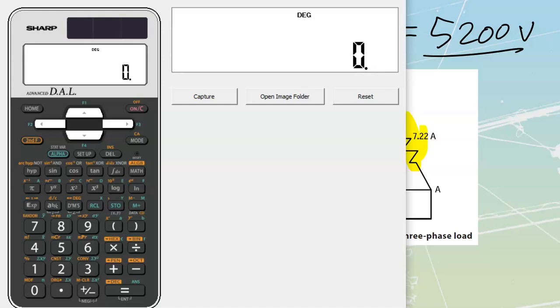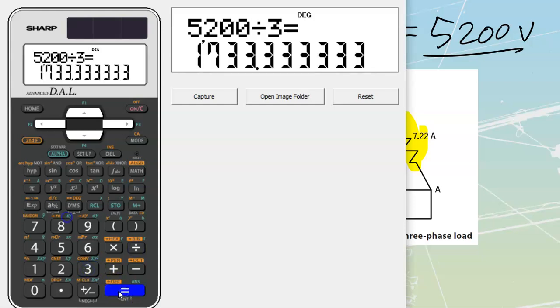We know how many total VA that we have, 5,200 VA. And if we take that 5200 VA and we divide it by the number of phases that we're putting it across in our load, that's going to tell us how many VA per phase.